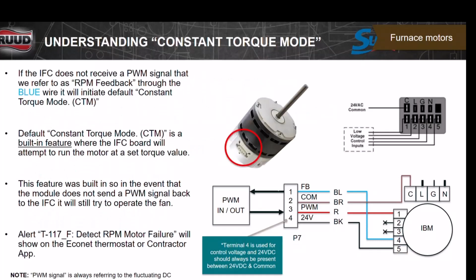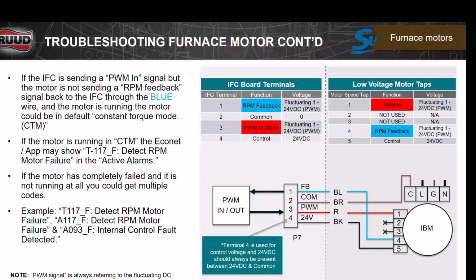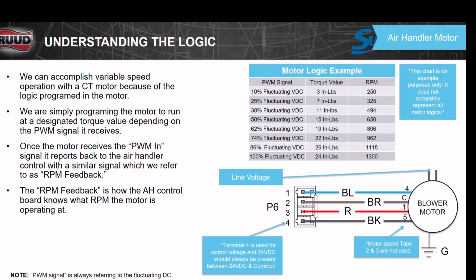So looking at the PWM signal that comes back from the motor, as you can see, the blue wire is what sends the RPM feedback. Of course, terminal 4 is used only for the 24-volt control back. It should be always present to the motor. The rest of the wires are communication wires back telling us what the motor is doing. A T117, that's detected not hitting the RPMs that it's supposed to hit, is what this is trying to tell you. So you can go back and check through your wires and make sure you have the correct voltage, correct feedback coming back from the motor here. This is the way that you can determine what the values of the torque are and where it's working as far as percentage of capacity.